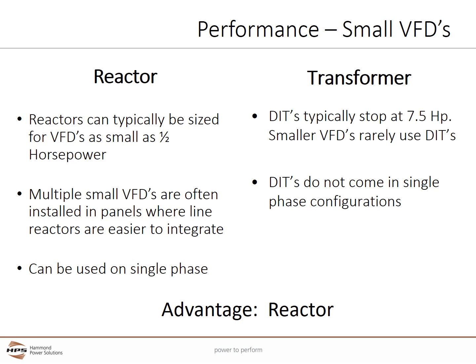within the VFD. Reactors are used 1 per VFD and can usually be sized for the VFDs down to 1/2 horsepower. In addition, stock line reactors can be used to power this small percentage of VFDs which will employ a single-phase input. DITs typically don't go below 7.5 horsepower and do not come in single-phase configurations. As a result, due to performance, size, price, and availability, line reactors are preferred for smaller VFDs below 10 horsepower.